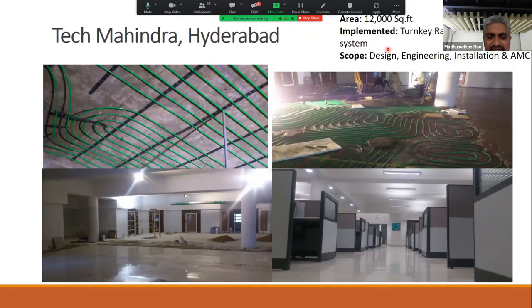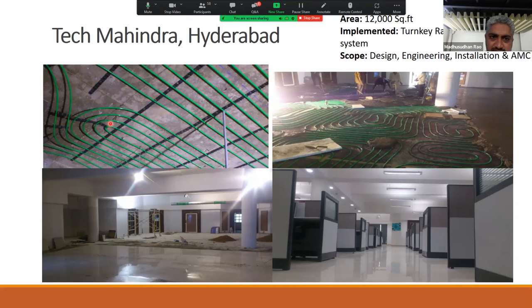This is a retrofit that we had done, where the piping was done on the ceiling. This is the ceiling part, and then it was completely plastered. So the heat exchanger was on the ceiling. This is the ceiling cooling that I was talking about. And then there is floor cooling also, where the pipes were embedded in the screed. And this is the final look and feel. Of course, fan coil units were used for delivering the treated fresh air into the space.